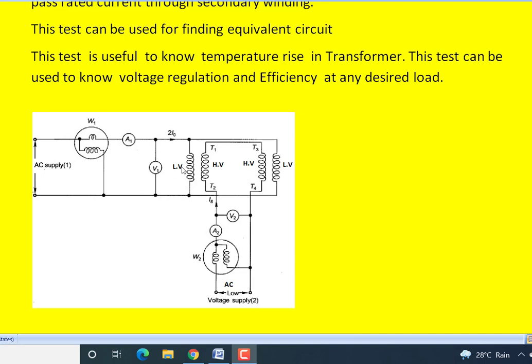So when we apply the rated voltage to the primary side and the secondary windings are in series opposition, then the voltmeter V2 shows zero reading. That means they are in phase opposition: the voltage induced in this and the voltage induced in this are the same in magnitude, but their polarities are in opposite direction. Once we get that condition, we have a small variable supply, an autotransformer. Then we change this voltage in such a way that this ammeter reads the rated current of the HV winding, meaning the secondary winding of the transformers.